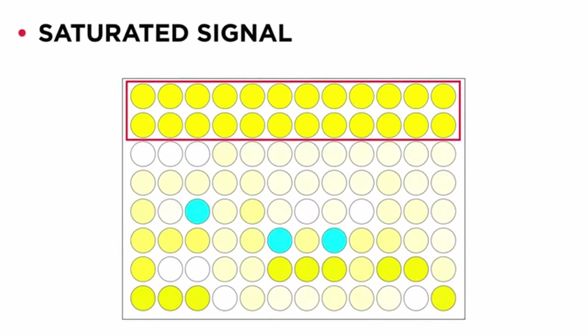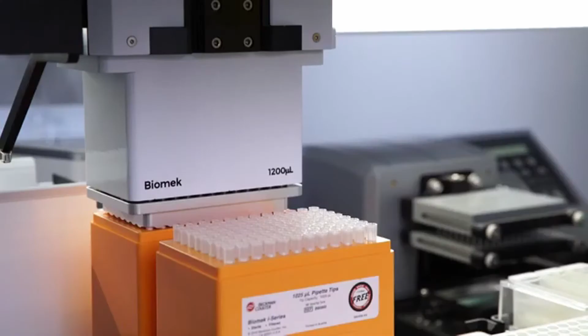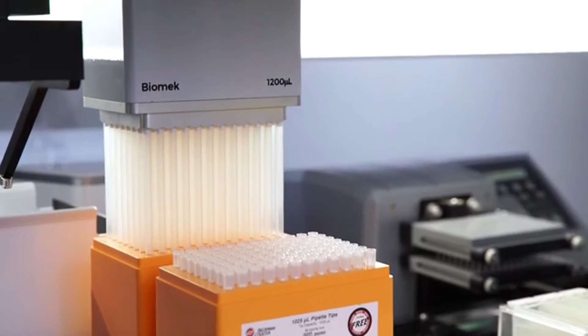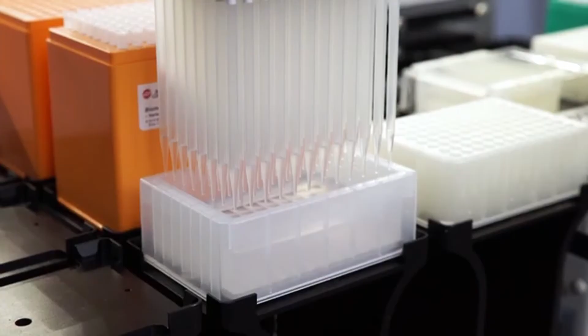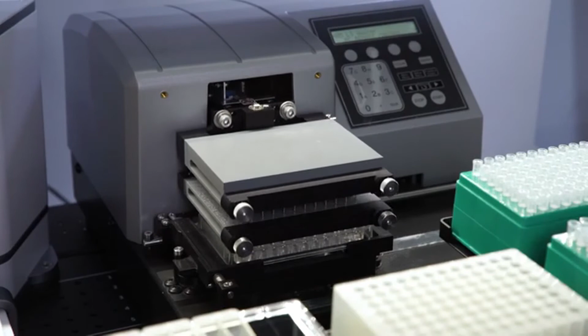Wash steps are repeated between each step of ELISA to remove unbound material. Inadequate washing creates a saturated signal resulting from nonspecific binding. Manual washing is time-consuming and cumbersome. Fortunately, Biomek liquid handlers come with a large volume multi-channel head with the capability to wash 96 or 384 samples at one time. In addition, plate washers can be readily integrated to the Biomek for high-throughput applications.